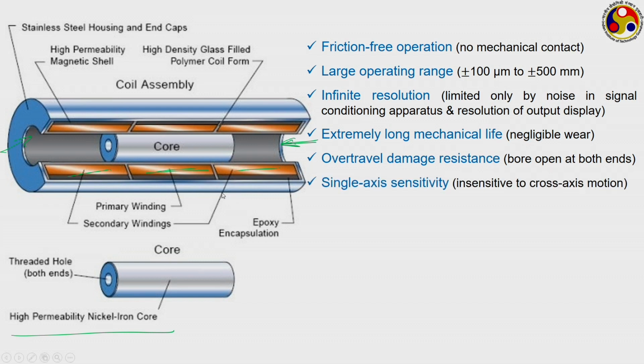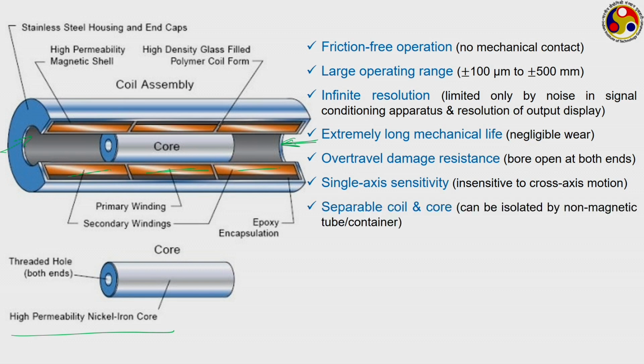Now, single axis sensitivity. Generally the core moves only in one particular direction, thereby sensing displacement only along that direction. It is often immune to any transverse motion or vibration. The core and coils can easily be separated if required. Suppose we want the core to move in some highly pressurized fluid, then we can separate the coils from the core by using a non-magnetic shell or tube, so that the pressurized fluid and the core remain inside that tube and the windings remain outside, thereby protecting the windings from the high pressure.